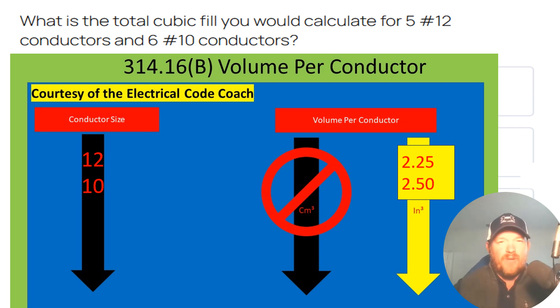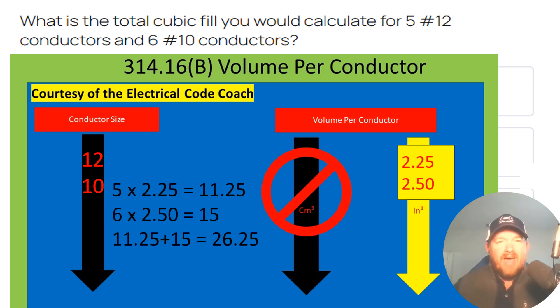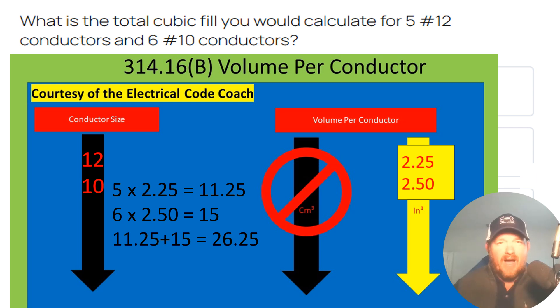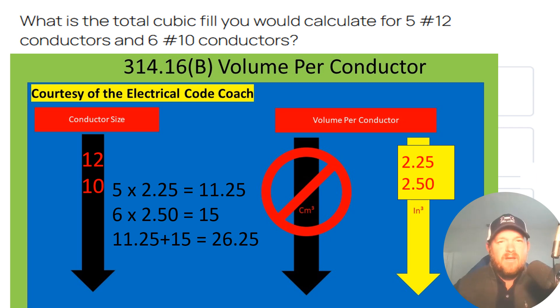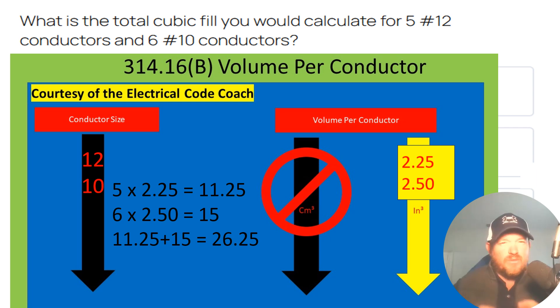All we have to do is some simple math. We have 5 number 12s, and we're going to multiply that by 2.25. Then we have 6 number 10s, and we're going to multiply that by 2.50. When we total that up, we find that these conductors are taking up 26.25 cubic inches of this box.